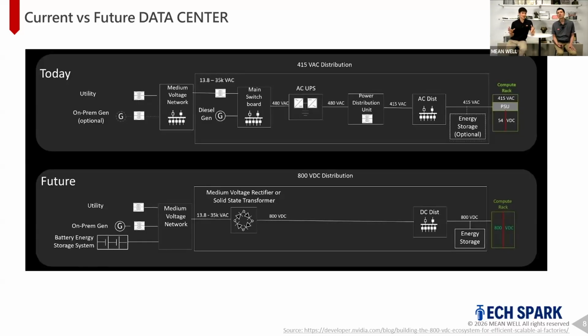The thing about this infrastructure is that in between that AC to DC step down, there's actually a UPS system, an AC UPS system, the one we looked at earlier. So what happens here, due to the AC bypass, going from 480 to 480, there's actually a little bit of power loss, which can be up to about 3%. And when you factor in the scale of these data centers...